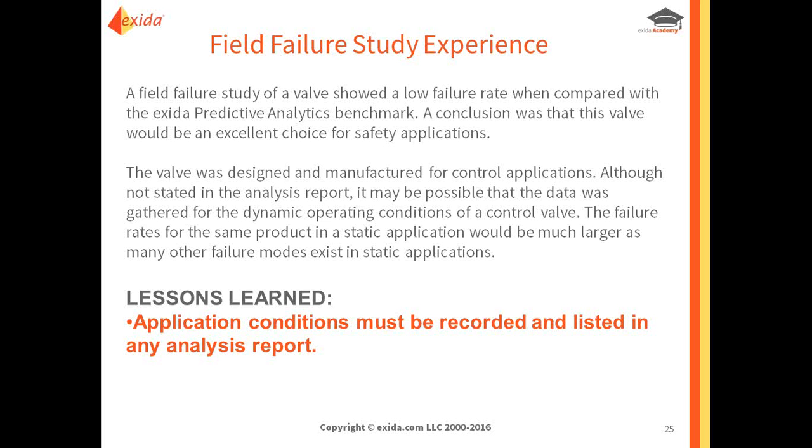All right, well, I do have a question that's on this topic. The question is, did this example use a control valve in an SIS application with a separate solenoid? Well, we do not know. Since the application conditions were not recorded in the failure reports, we had insufficient information, but someone used that info to calculate a failure without even knowing the application.